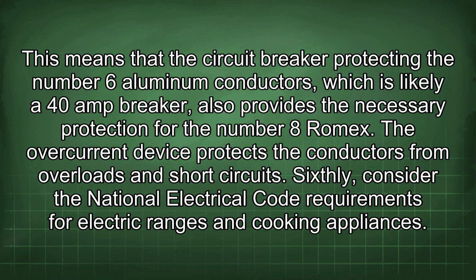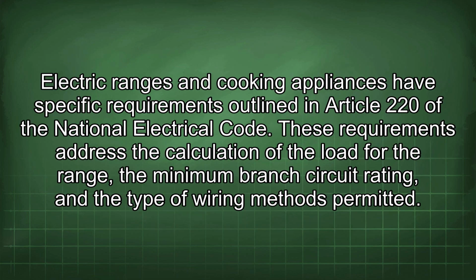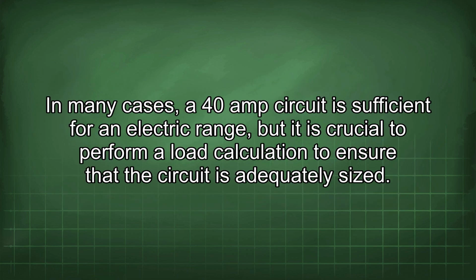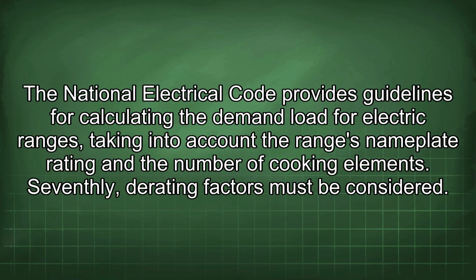Sixthly, consider the National Electrical Code requirements for electric ranges and cooking appliances. Electric ranges and cooking appliances have specific requirements outlined in Article 220 of the National Electrical Code. These requirements address the calculation of the load for the range, the minimum branch circuit rating, and the type of wiring methods permitted. In many cases, a 40 amp circuit is sufficient for an electric range, but it is crucial to perform a load calculation to ensure that the circuit is adequately sized. The National Electrical Code provides guidelines for calculating the demand load for electric ranges, taking into account the range's nameplate rating and the number of cooking elements.